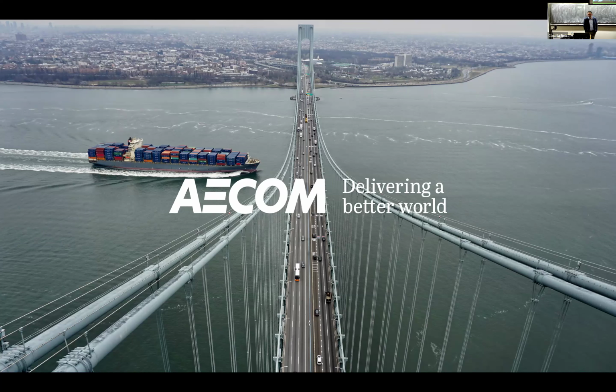Yeah, it was scheduled in there, so it had to be done, it was part of the work, which is a good thing. Repairing that many wires is really good for the cable, so now it's dehumidified. We could tell, based on the oiling that was done, it definitely helped the situation, but after so many inspections it proved things were still slowly going in the downward direction. It was time to put the dehumidification system on.